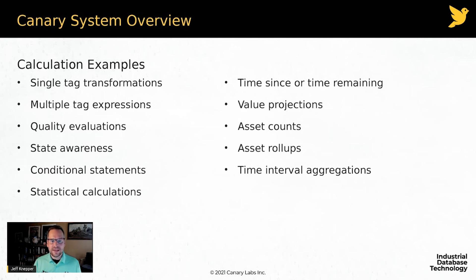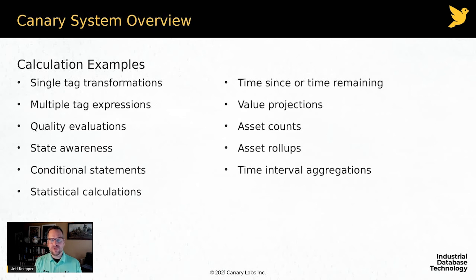Finally, time interval aggregations: I have a flow on my pump and I'd like to know not what the flow is right now, but what is the 60-minute running average of that flow, updated every 30 seconds.